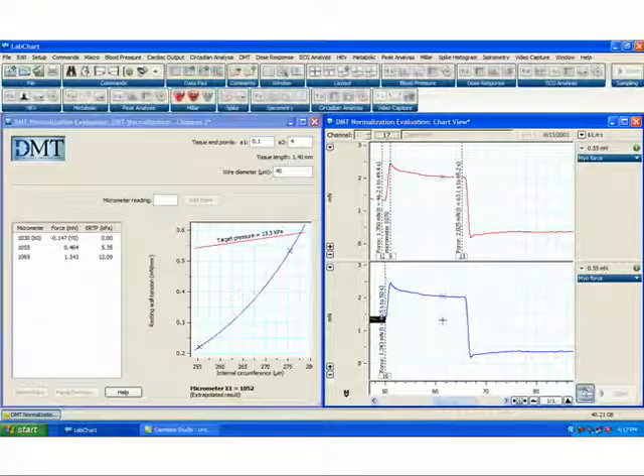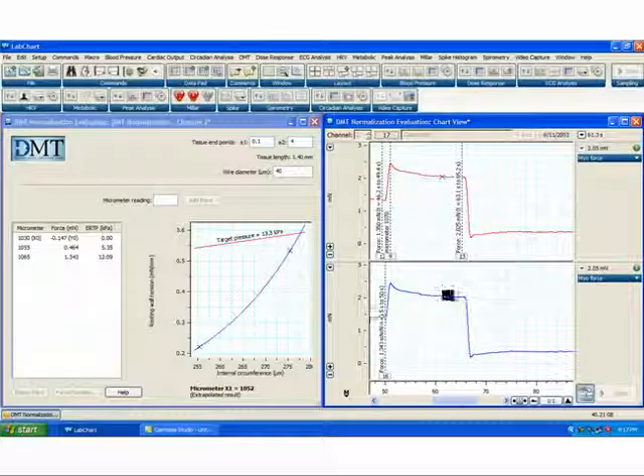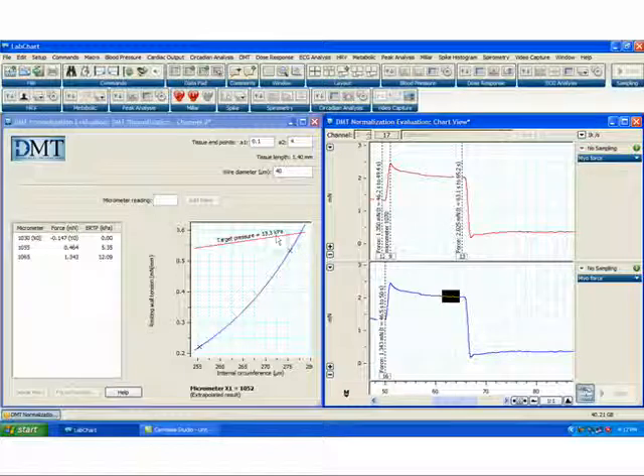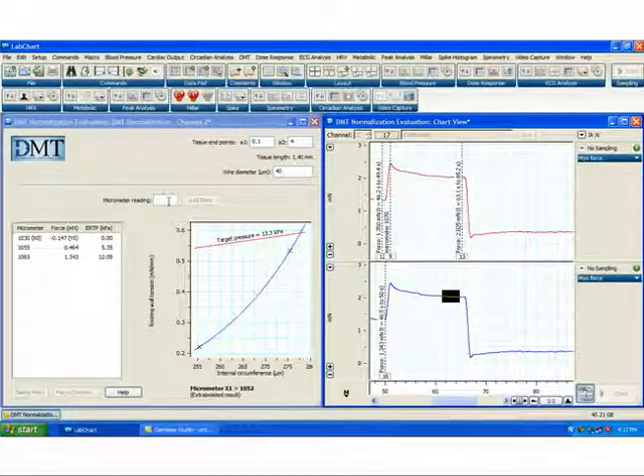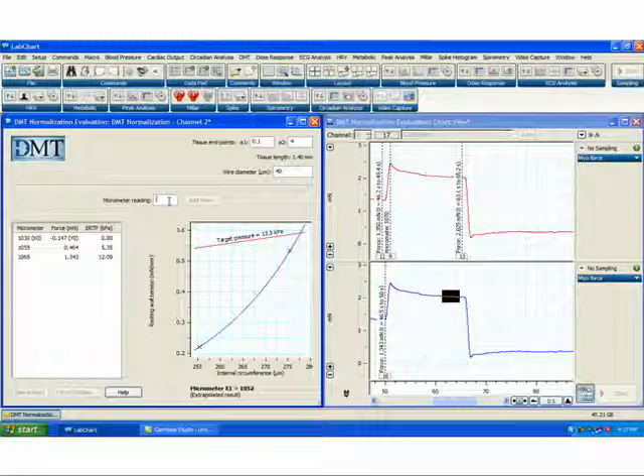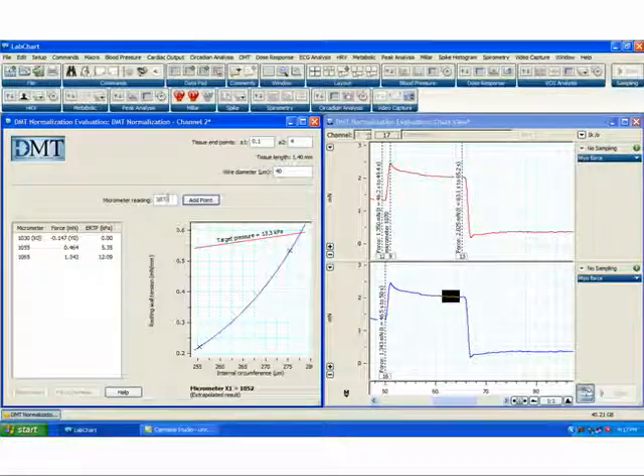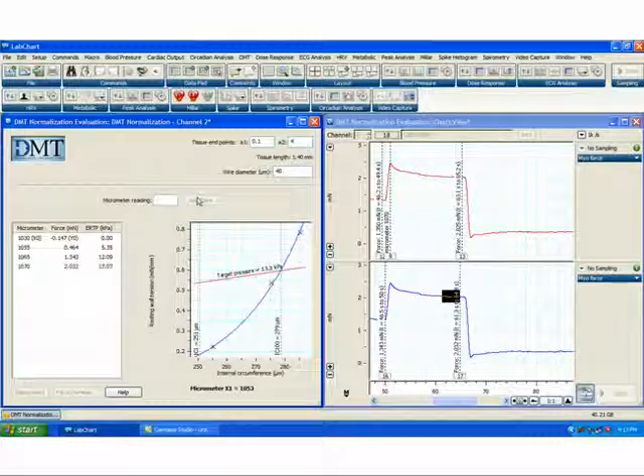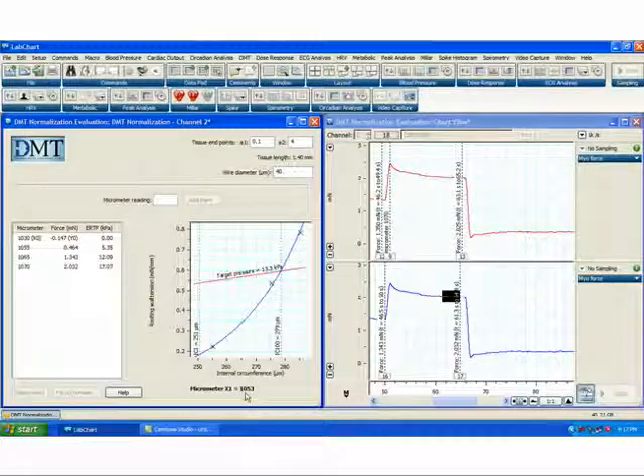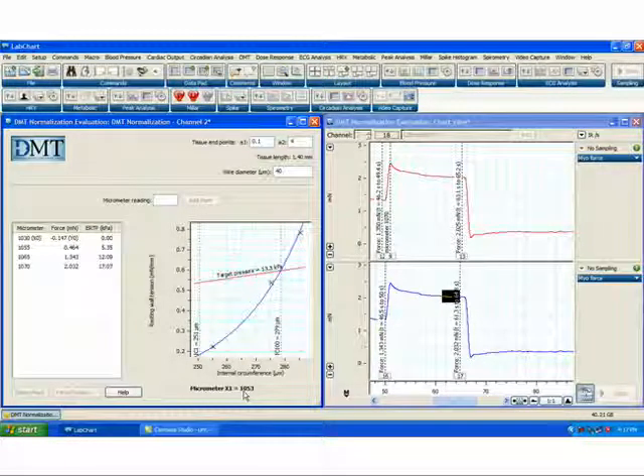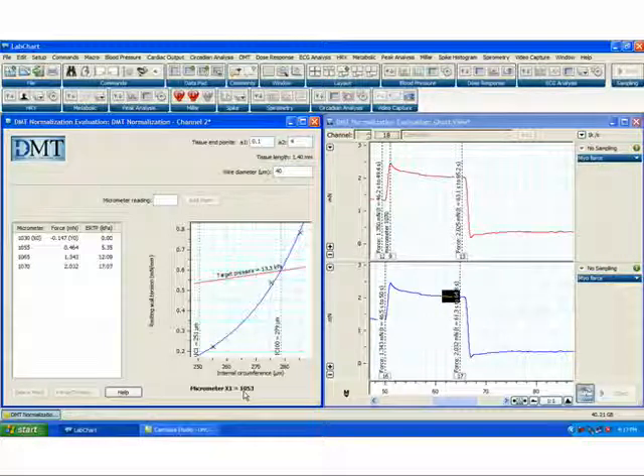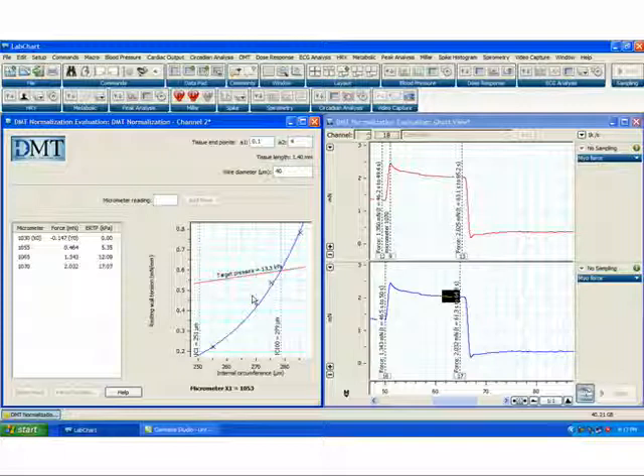Using more than three points, however, is recommended as it will make your normalization more accurate. Adding a fourth point with a micrometer reading of 1070 now tells us that our micrometer needs to be set at 1053, which is probably a more accurate value to reach the target pressure of 13.3 kilopascals.